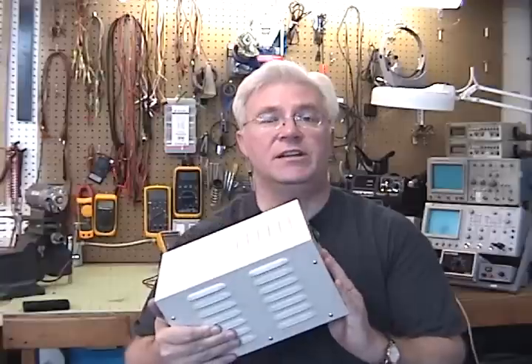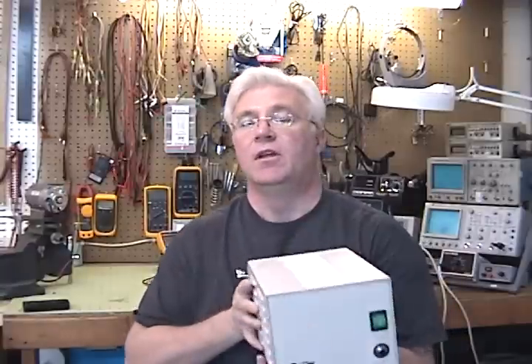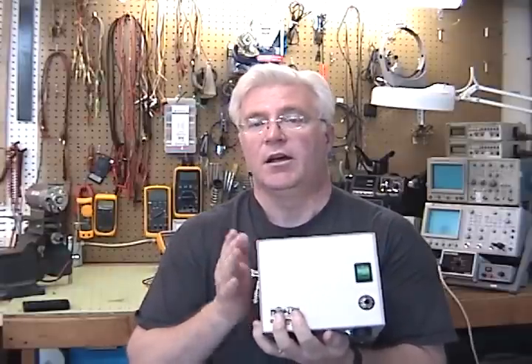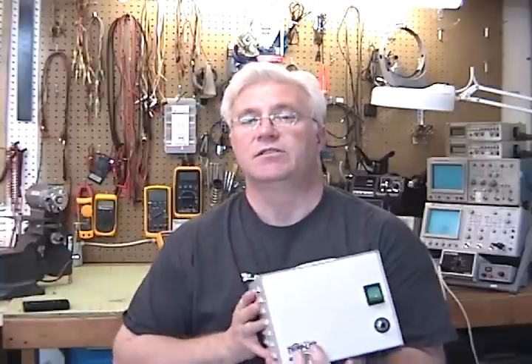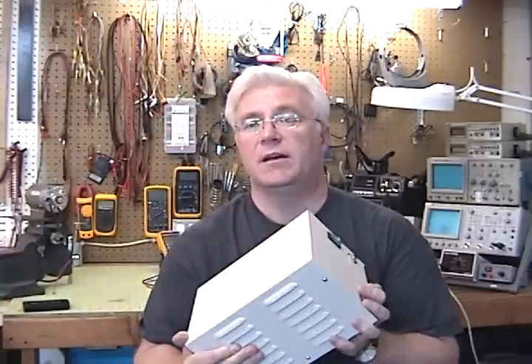What you need to do to change that, when you buy one of these publicly available isolation transformers, one which is rated for the amperage you need and want, is alter it so that it doesn't do that anymore. It's as simple as opening it up and taking off a little grounding strap that they put in there that straps the secondary transformer coil to ground. That thing weighs 40 pounds, by the way. By taking it out of the circuit, which I'll show how to do later, I'll even show the dangerous voltages that are there in a standard public isolation transformer with some tests coming up.